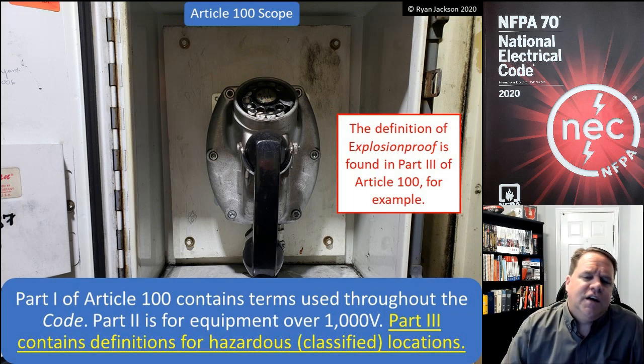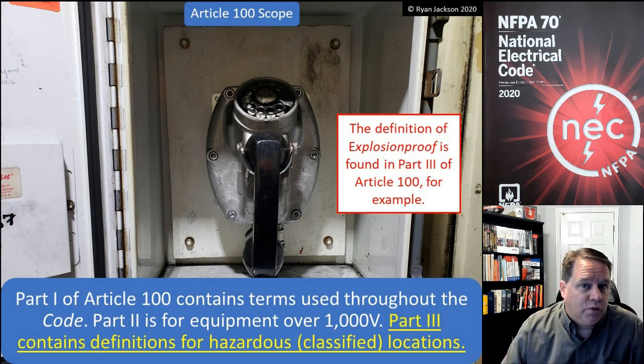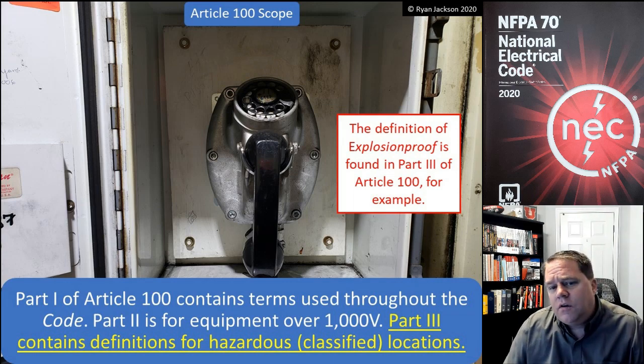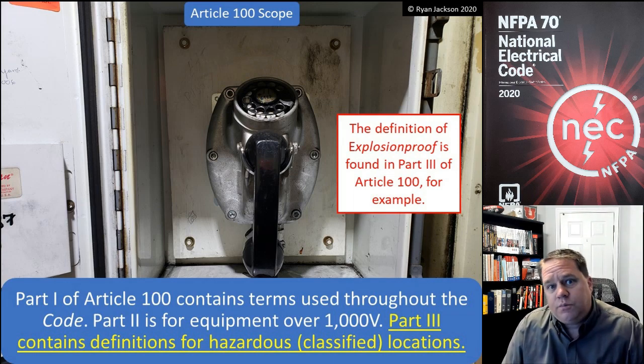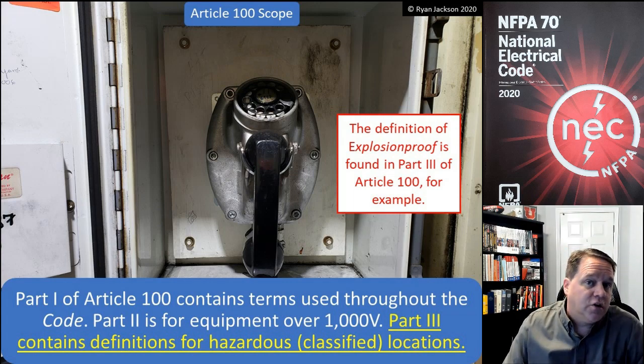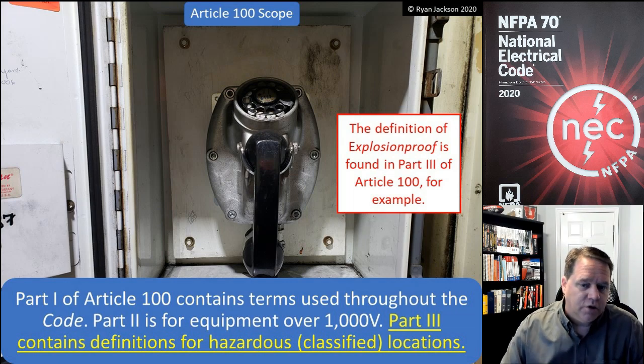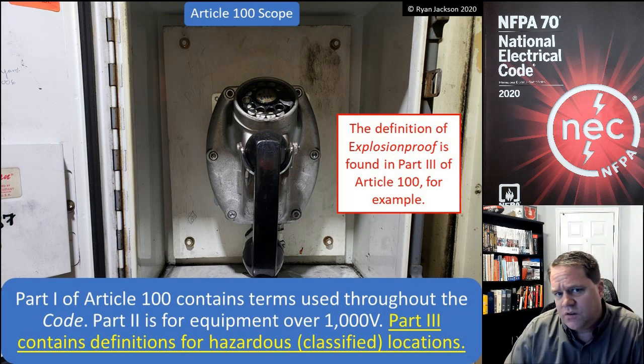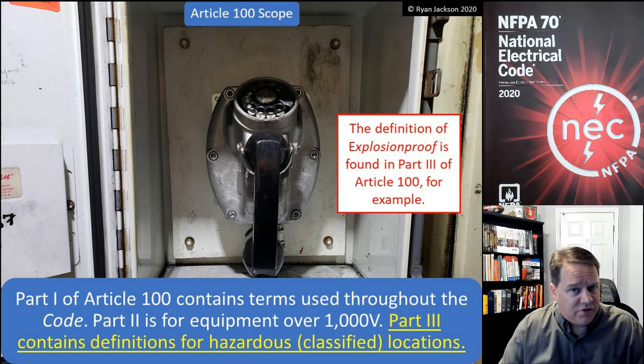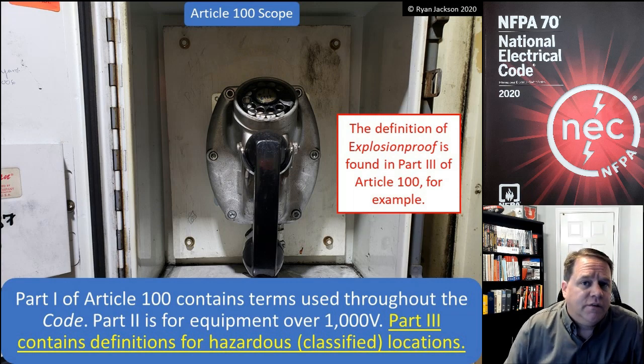Part three contains the definitions for hazardous or classified locations. What we're looking at in the picture is an explosion-proof telephone. If you're looking for the definition of "explosion proof," that is in Article 100 — but it's in Part three. That's where all the hazardous location definitions are: explosion proof, intrinsically safe, dust ignition proof, things like that. You'll want to find yourself in Part three of Article 100.